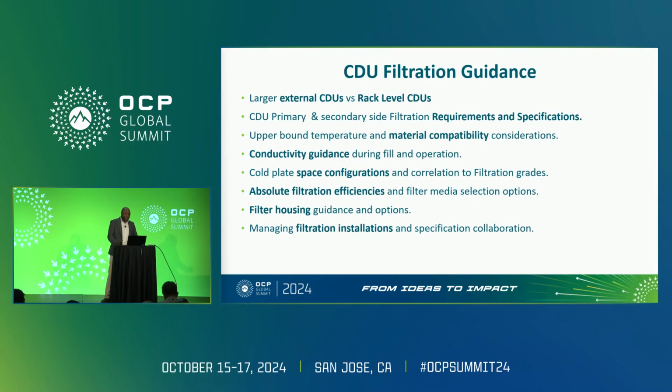As I said, it's important to protect tight fin spaces, and the filtration that you have in place should be based on the gap sizes of the microchannels. So always ask the filter manufacturer what the efficiency of the filter is. Hands up, how many people use filters in the room? Okay, a few hands. How many people know the efficiency of their filters?